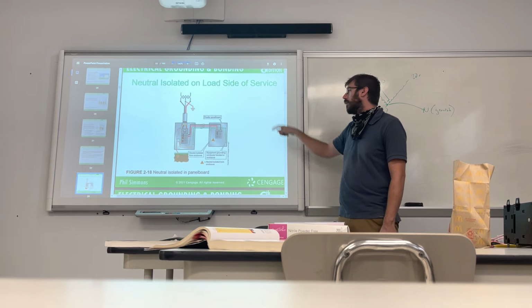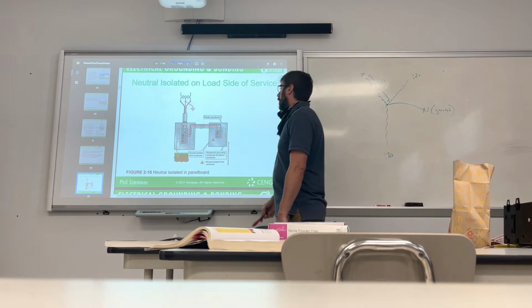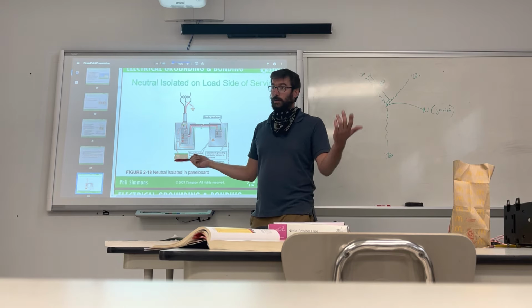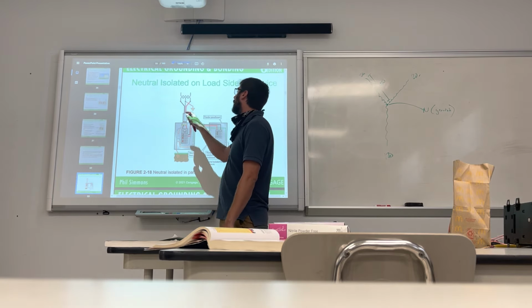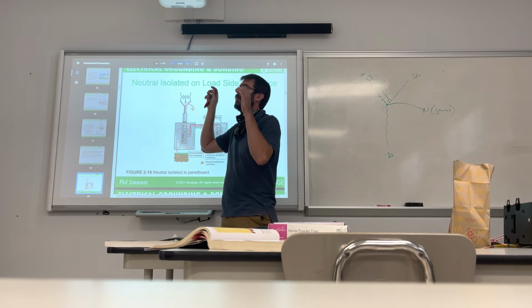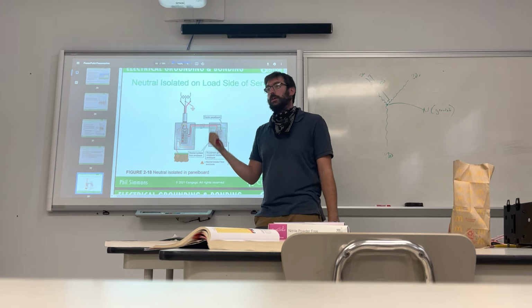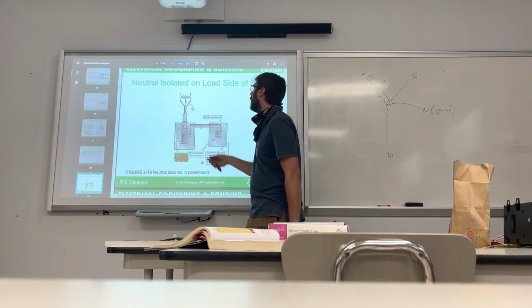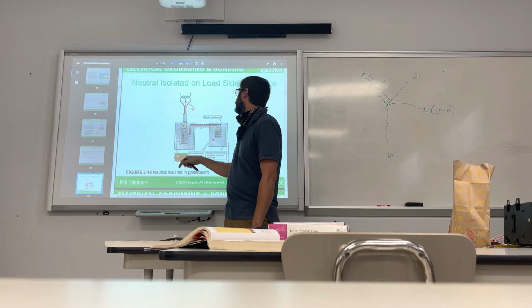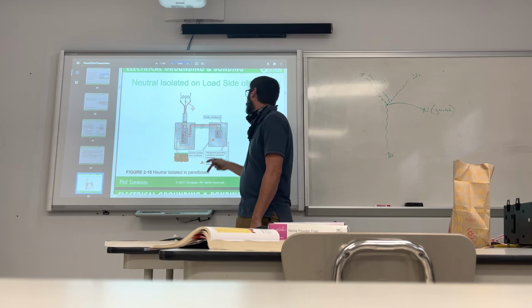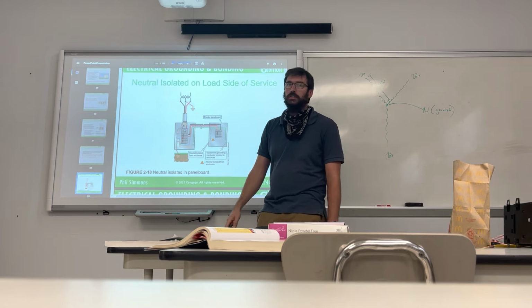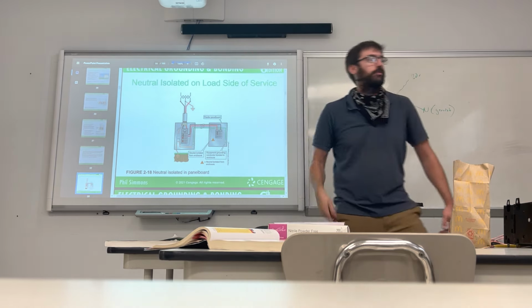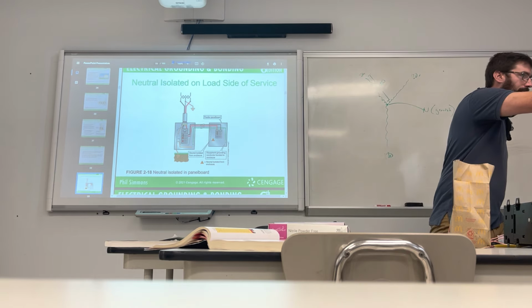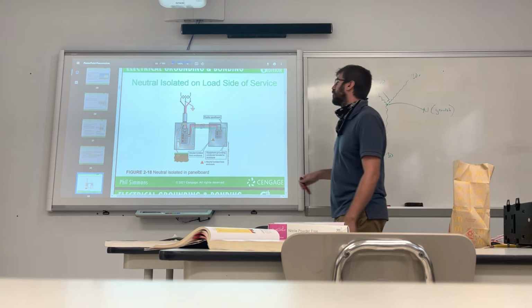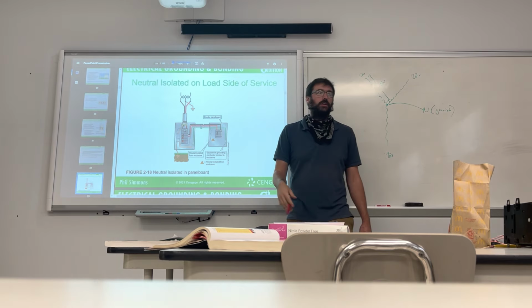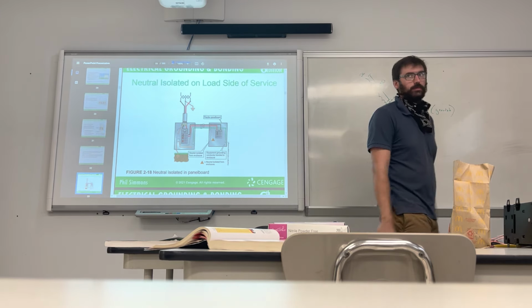Well, once again, let's talk about this for the 30,000th time. The neutral up there, the transformer, whether it's on a pole, in your front yard, on your roof, or in a cave, it's going to be grounded off the transformer. It's also going to be grounded in your main panel box, but that sub panel is isolated. The ground and the neutral are separate to prevent... What? I'm sorry, I was typing. All right, sorry. What kind of current don't we want going across that ground? Objectionable current. Okay.